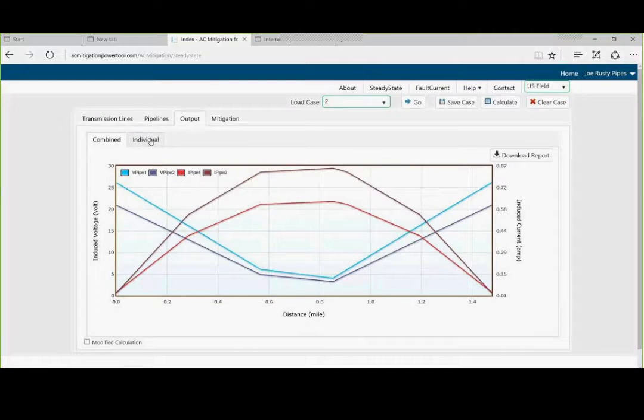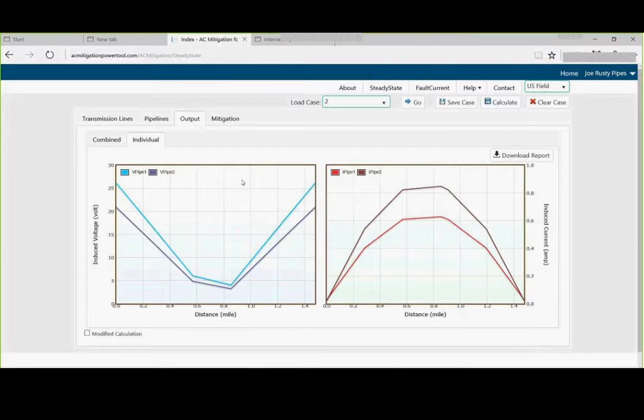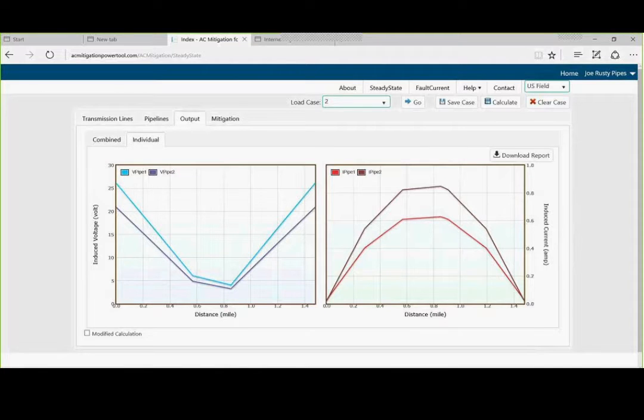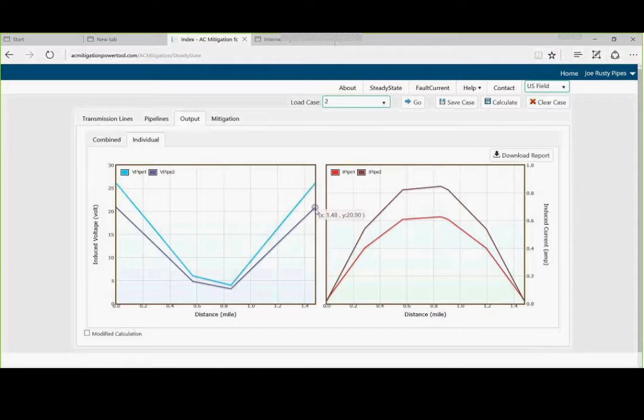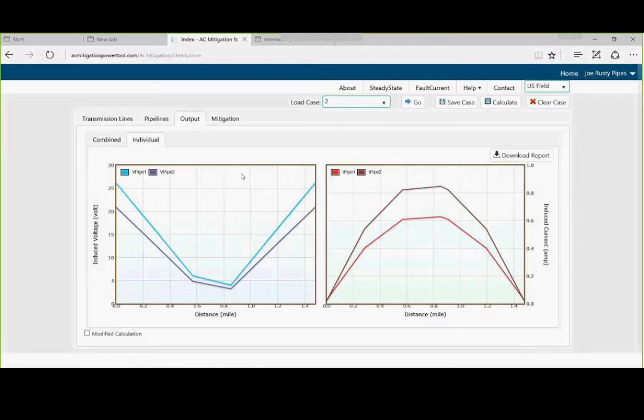To avoid the confusion, let's take a look at it. So, it looks like pipe one, which is the closest one, has about a little over 26 volts on each end. And pipe two has about almost 21 volts on each end with potentials down near the bottom here, several volts. So, what would that tell us to mitigate? Where would we want to put our mitigation? Are we there yet? Absolutely. This is the beauty of this software.